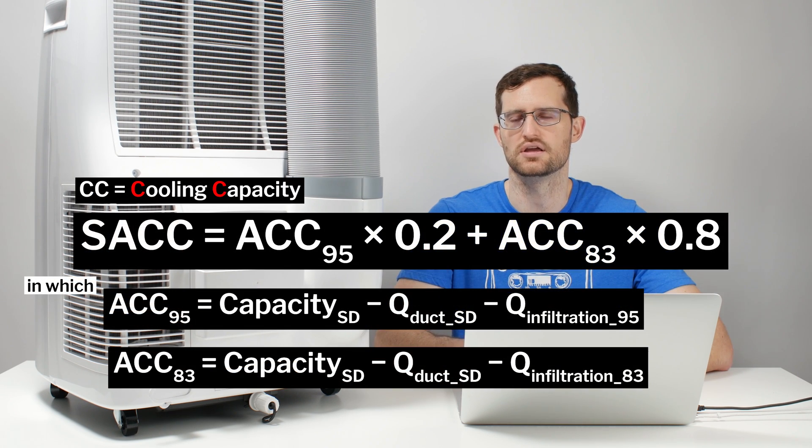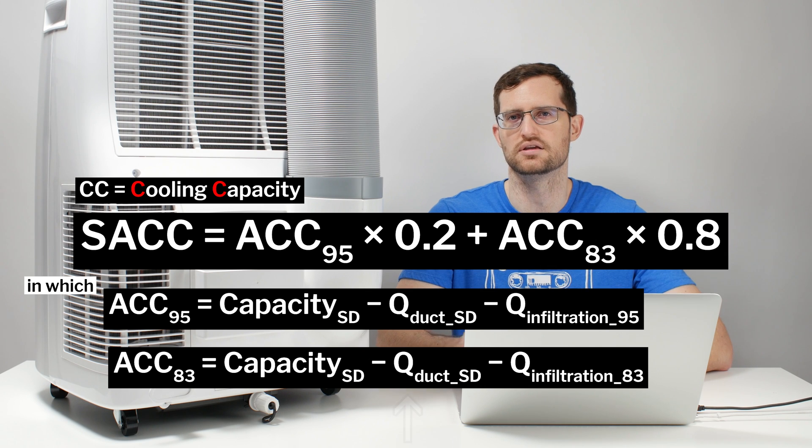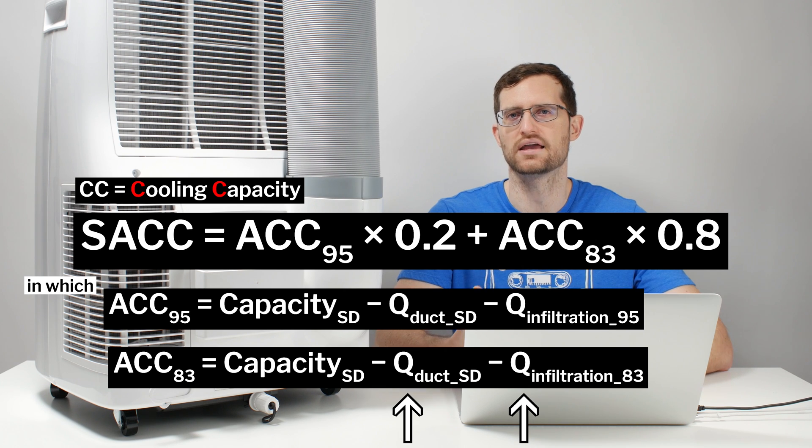Now, in recent times, we have new standards for measuring BTUs and that new standard is called seasonally adjusted cooling capacity. And using seasonally adjusted cooling capacity, we can now see the true cooling capacity of these units because seasonally adjusted cooling capacity, SACC for short, actually subtracts the heat added by the ducting and the heat added by infiltration air from the overall BTU number to give us a more accurate BTU number that we can use to compare different units.